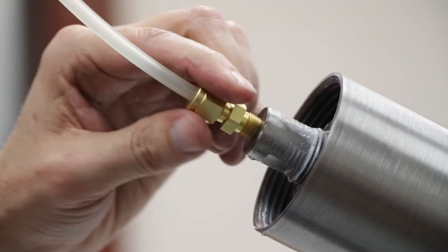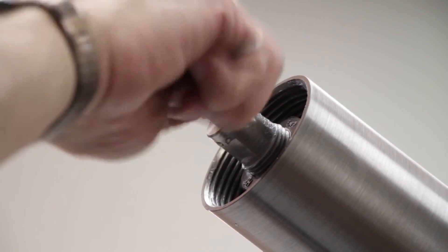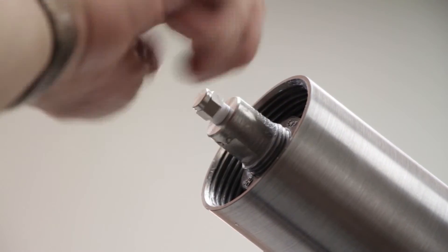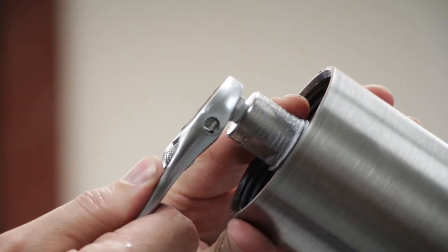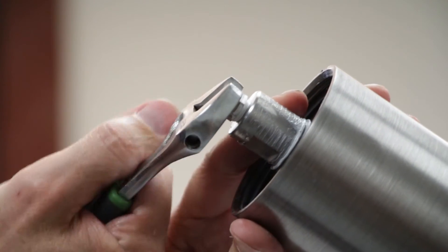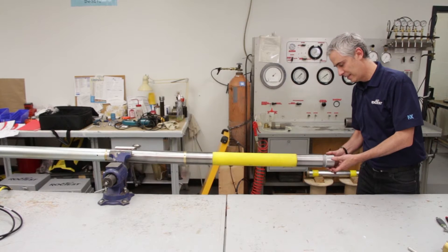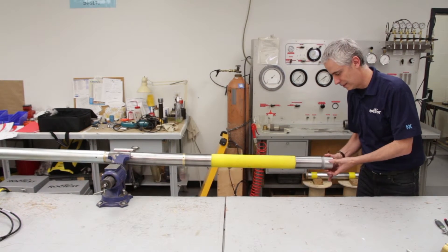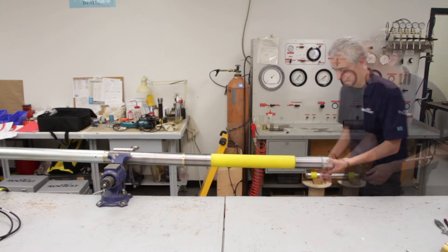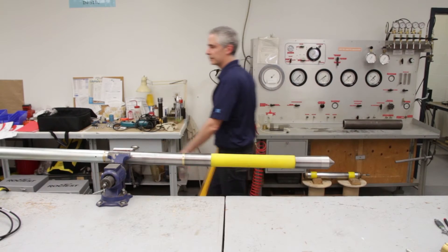Once this is accomplished, fully retract the piston. Remove the tubing, put 3 to 5 layers of Teflon tape on the plug's threads, and screw the saturation plug back onto the steel core. Once this is done, screw the stainless steel conical end cap back onto the probe. Your saturation is now complete.